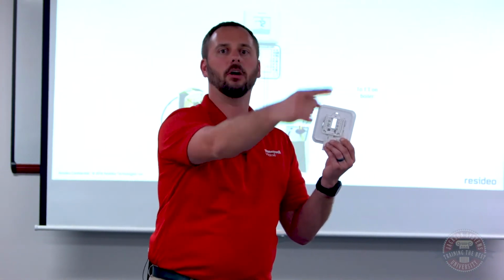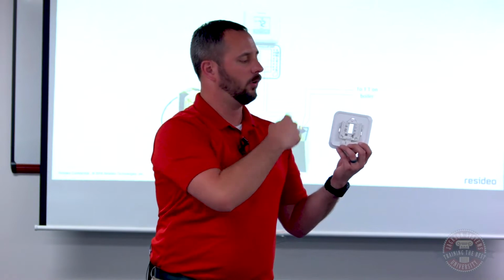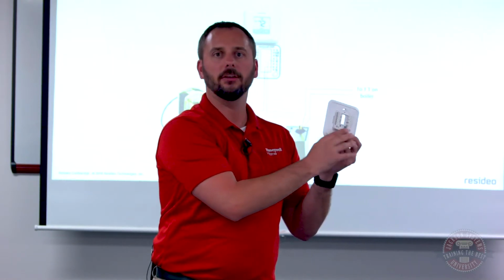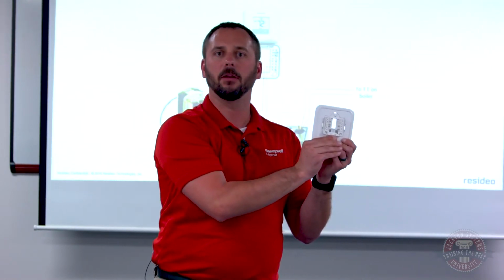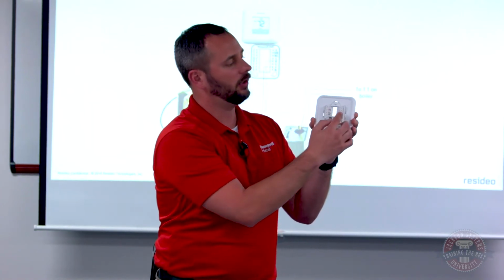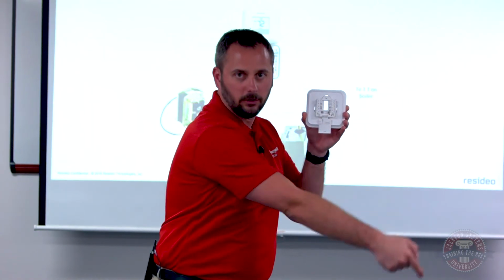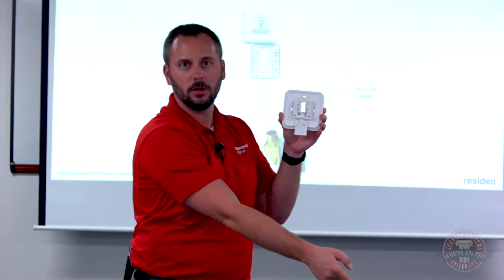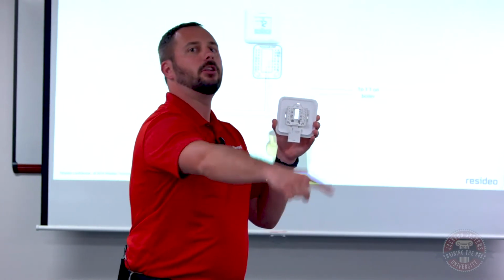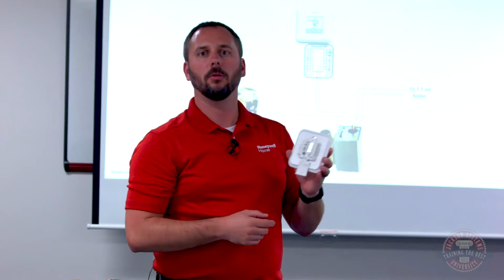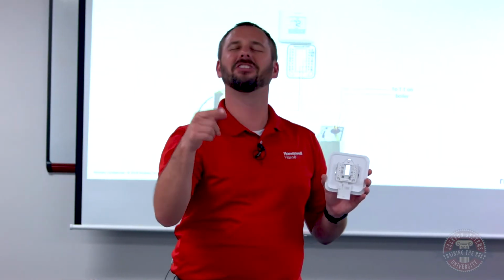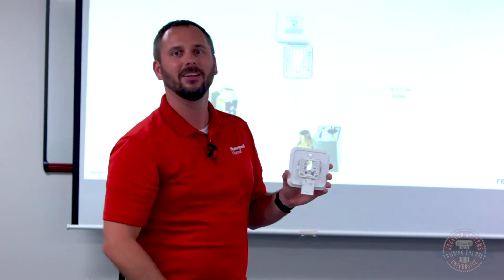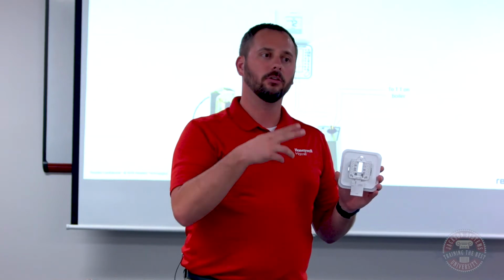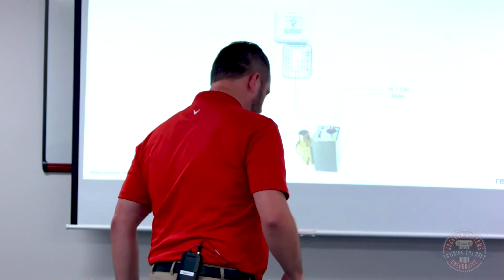So we've now completed our circuit. What happens is we basically take power up to here. It sits on the thermostat waiting for something to happen. The temperature drops, clicks the relay. It's now sending 24 volts out across W down to the motor. And then you have to complete the circuit. So the other side of the motor has to go back to the zone valve. I'm sorry, the other side of the zone valve has to go back to the transformer, and you're going to hook it on C. So now you've used both sides of the transformer. That's our simple two-wire zone valve system.